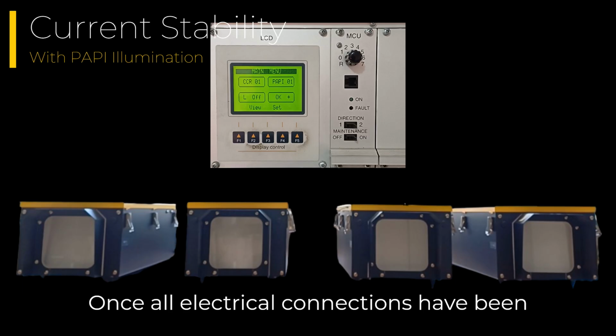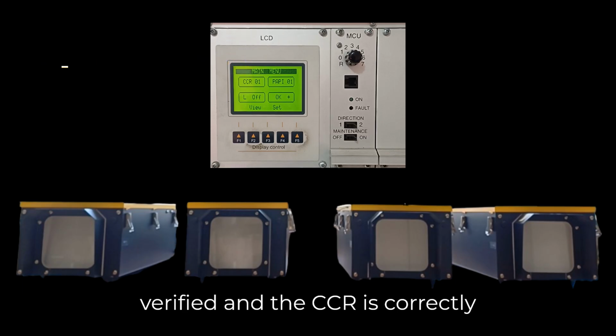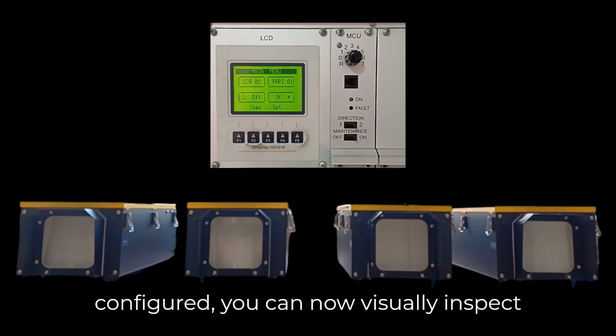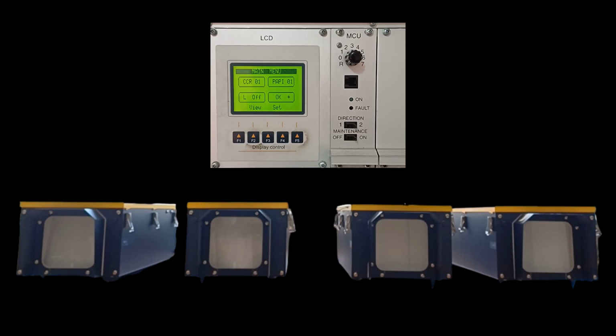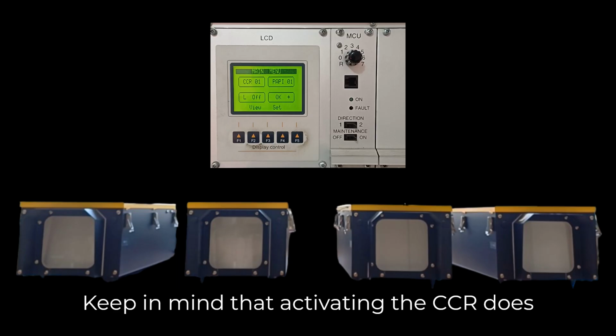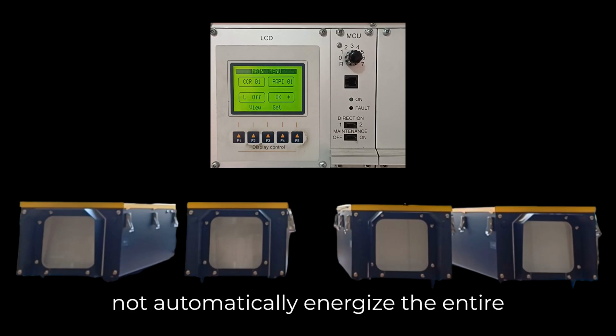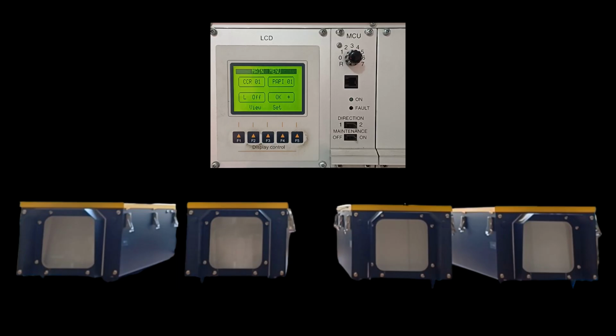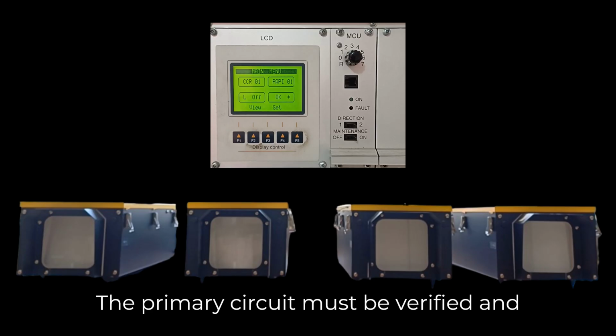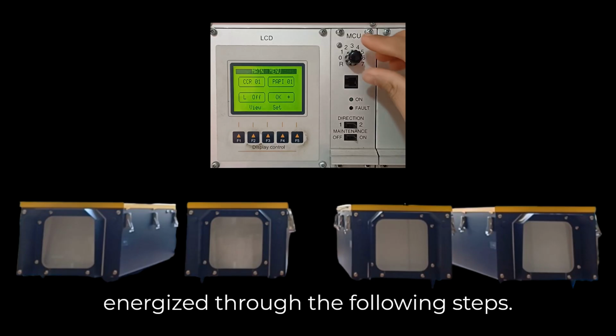Once all electrical connections have been verified and the CCR is correctly configured, you can now visually inspect the PAPI illumination. Keep in mind that activating the CCR does not automatically energize the entire PAPI system. The primary circuit must be verified and energized through the following steps.